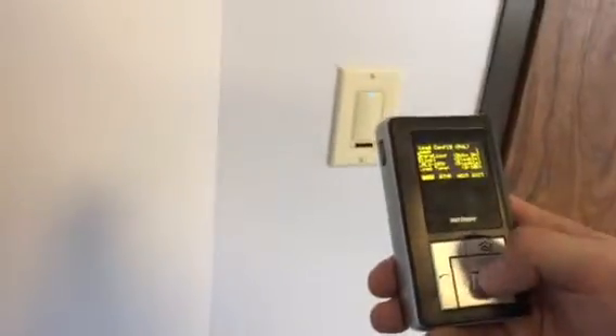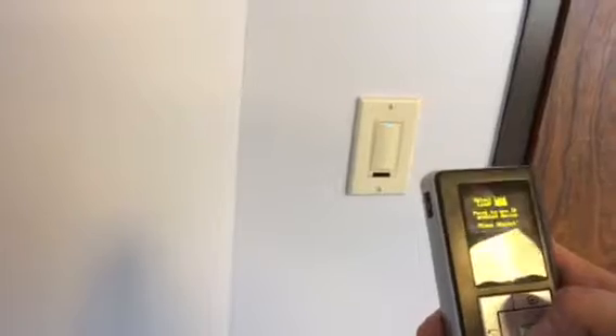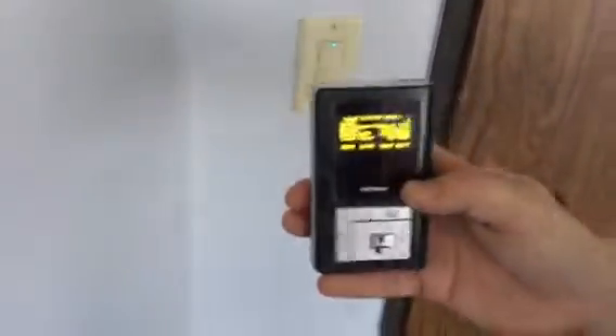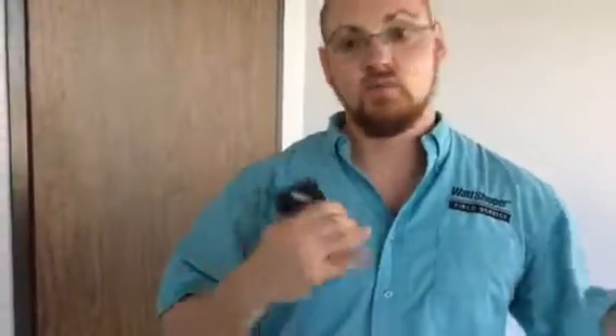If I make a change, I'd press send, or for this scenario I'm going to go next, because I'm going to show you how to make load 2 auto on. I'm going to press select, it's going to come back, and if I had a set of lights tied to this load, those lights would currently be on. So whatever load is displayed in the load config, that light should be on, all the others should be off, so you can easily identify what lights you're currently looking at.